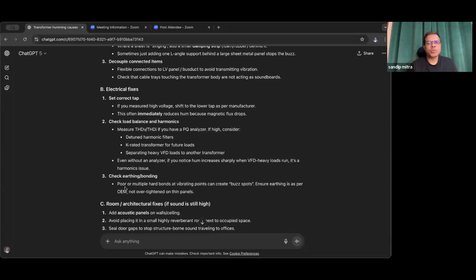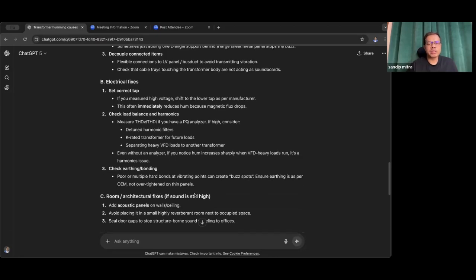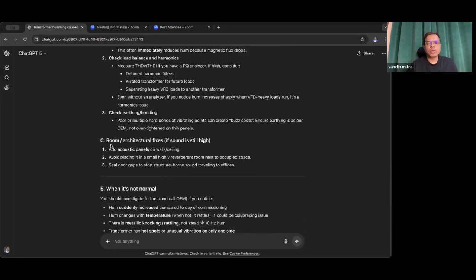Check earthing. Poor or multiple hard bonds at vibrating points can create buzz spots. Ensure earthing is as per OEM, not over tightened on the thin panels. And room and architectural fixes: if sound is still high, add acoustic panels on walls or ceiling. Avoid placing it in a small, highly reverberant room next to the occupied space. Seal door gaps to stop structure-borne sound traveling to others.